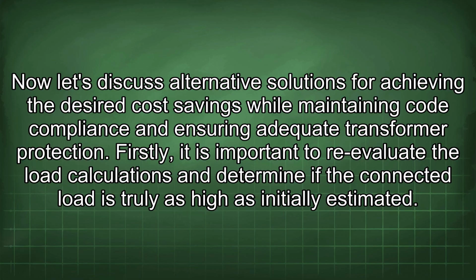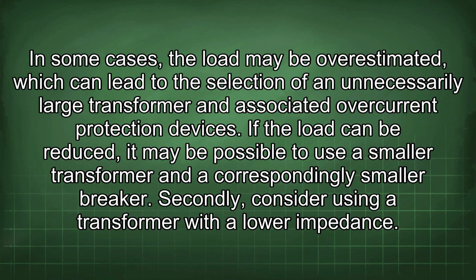adequate transformer protection. Firstly, it is important to re-evaluate the load calculations and determine if the connected load is truly as high as initially estimated. In some cases, the load may be overestimated, which can lead to the selection of an unnecessarily large transformer and associated overcurrent protection devices. If the load can be reduced, it may be possible to use a smaller transformer and a correspondingly smaller breaker. Secondly, consider using a transformer with a lower impedance.